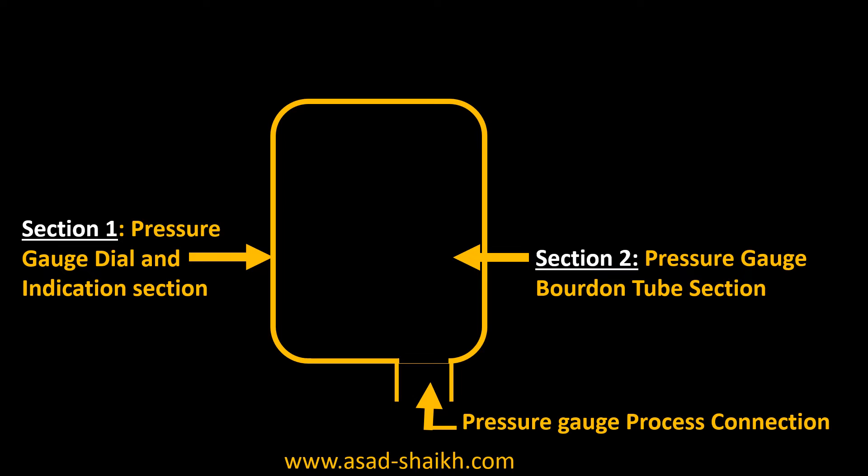Now the interesting question is: what if at high pressures the Bourdon tube ruptures and the process fluid comes out from the Bourdon tube? That fluid would eventually find its way out through the gauge dial, and this could injure the plant personnel who is in front of the pressure gauge. This would be a very hazardous scenario.